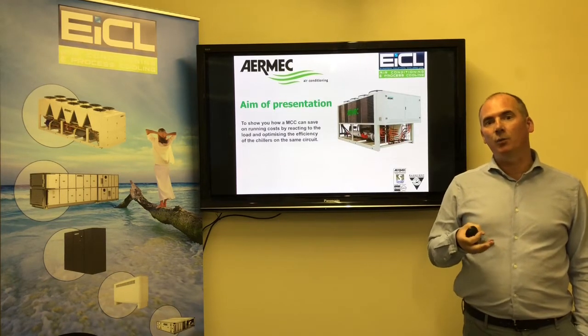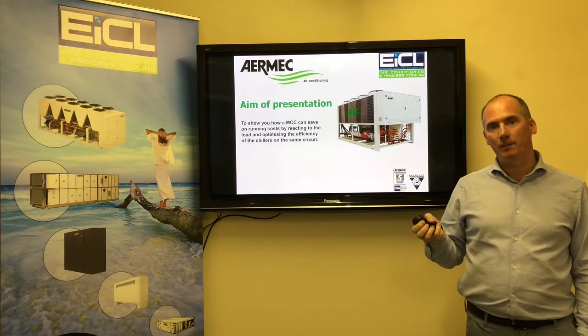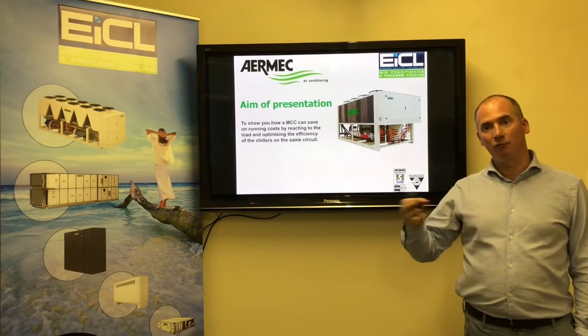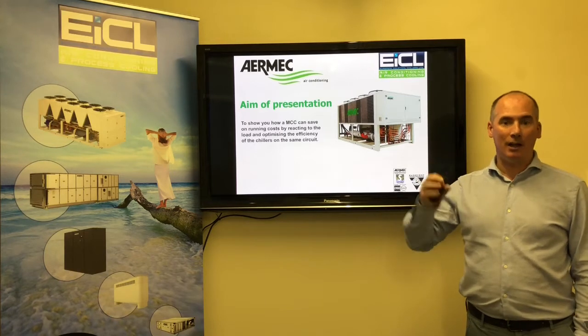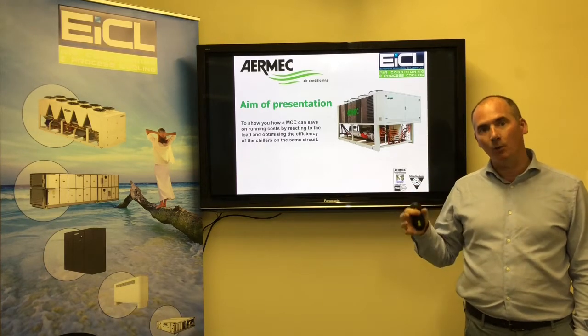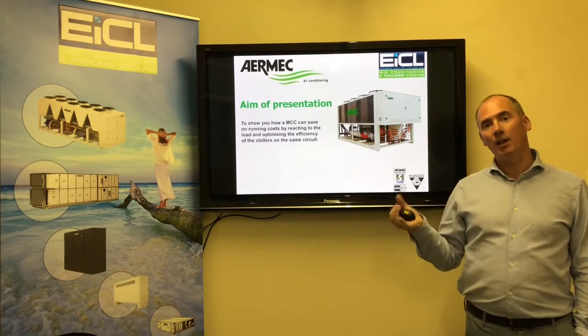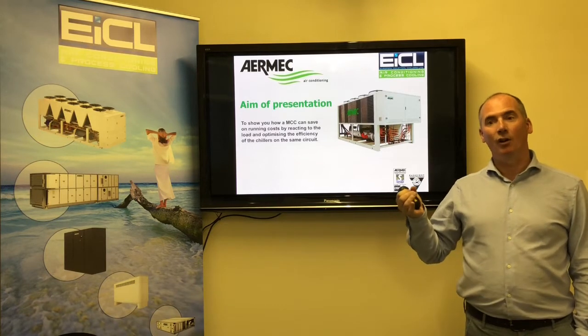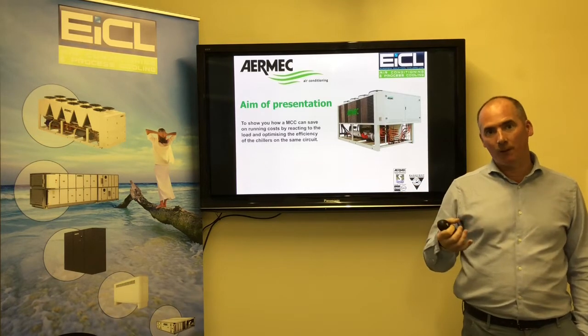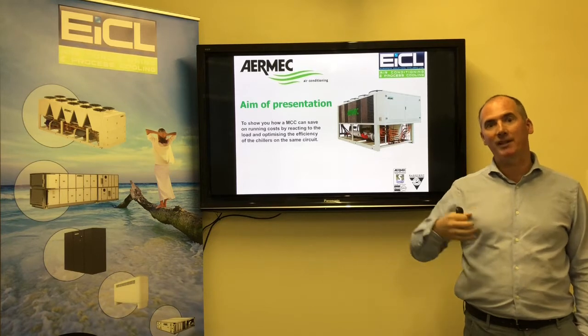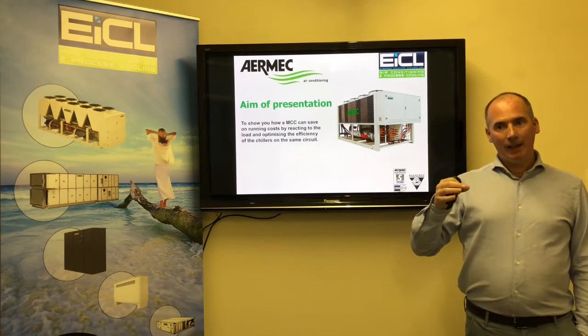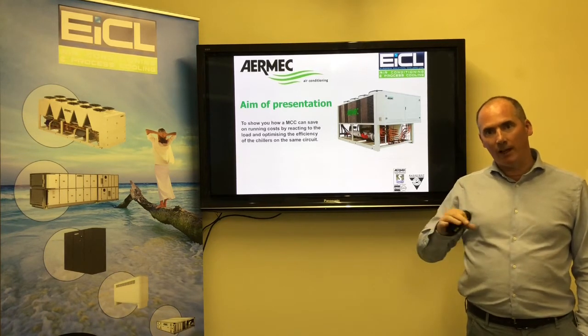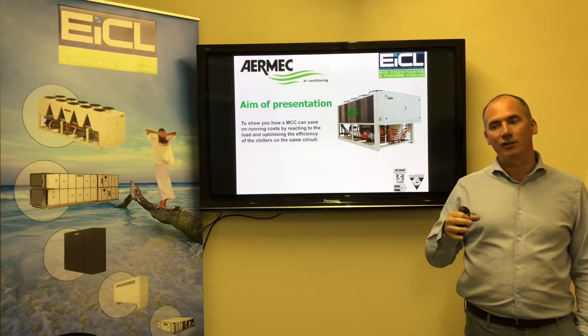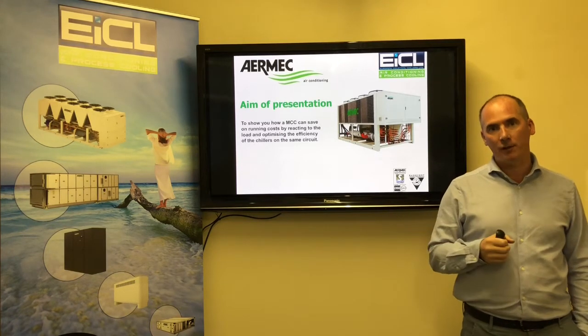Unlike historically, where you would have maybe 2 or more chillers in a system, the first chiller would typically be run and then maybe you would have a duty assist or duty standby with the other chiller, and you would time to change them over at some stage unless there's a fault. If there was a fault, you get a signal typically back to the BMS that would bring on the other chiller. However, the problem with this design concept is that there's little or no regard for the part load efficiency.